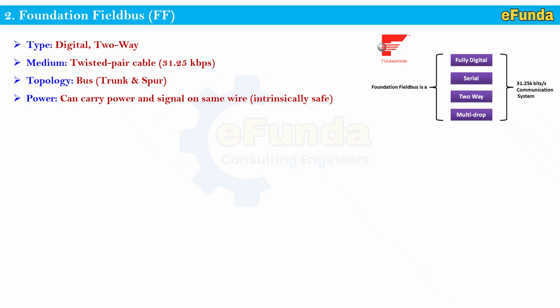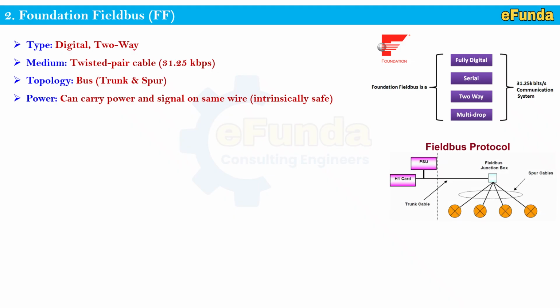One can refer to the fieldbus protocol, where the power supply unit, then the H1 card, is shown connected with a fieldbus junction box at a field through the trunk cable, and all the field transmitters or field devices are connected to the junction boxes through the spur cable. This is how the structure of a fieldbus communication is.